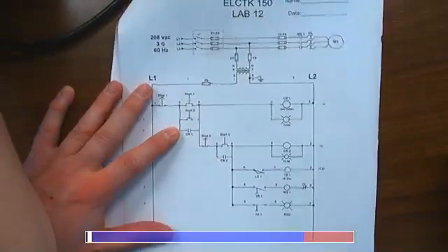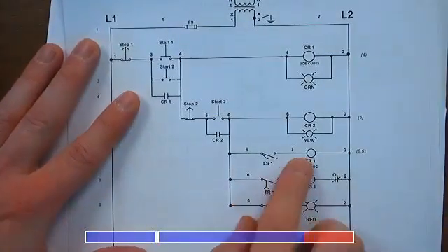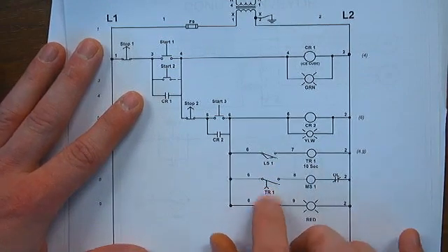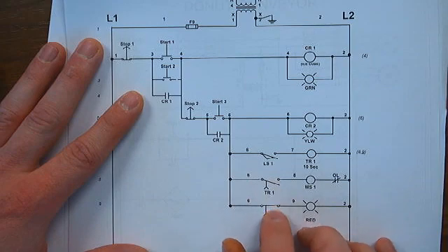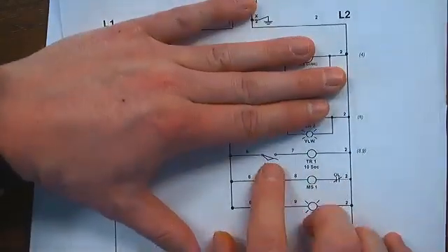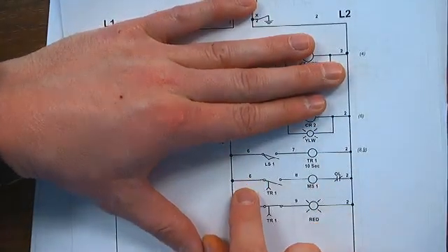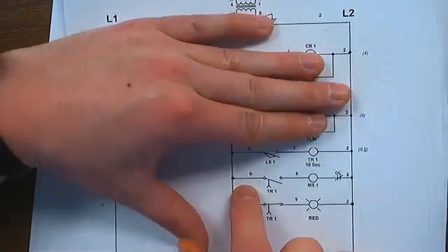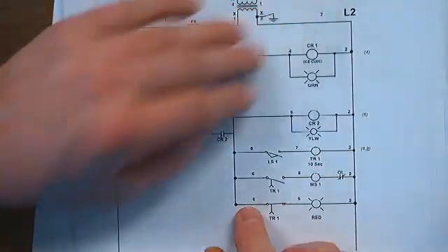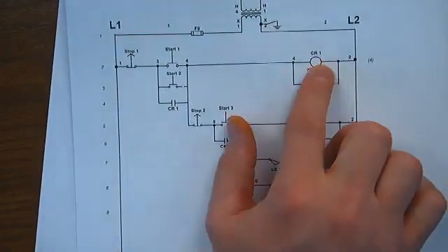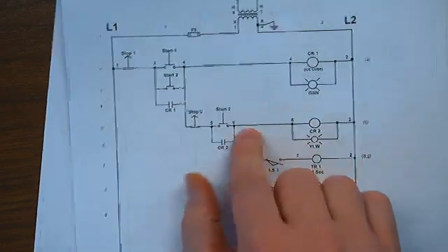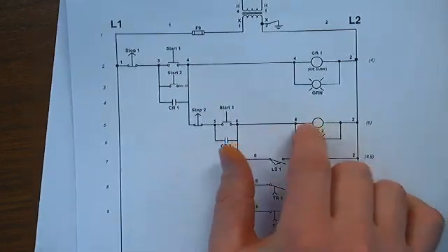Lab 12. So your coil for your timer's right here. It says 10 seconds. Try to get it close if you can. Are these on delay or off delay? On delay, because they're pointing up. Normally open, normally closed. So basically what will happen when you get to this point in the print, you close that limit switch, what happens? Timer starts. Nothing changes state until 10 seconds later. Then it looks like they want you to use an ice cube relay up here, CR2. You can use whatever you want, IEC or NEMA.